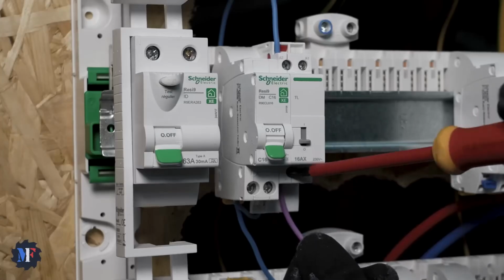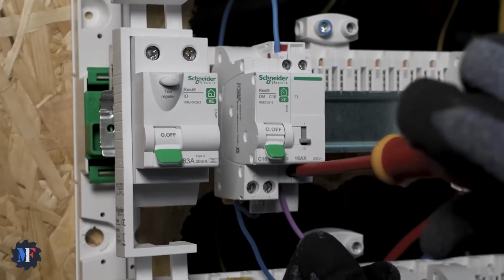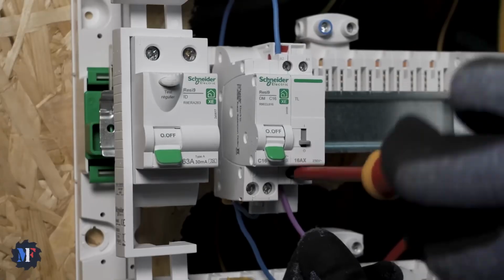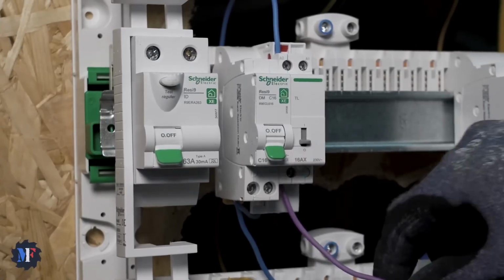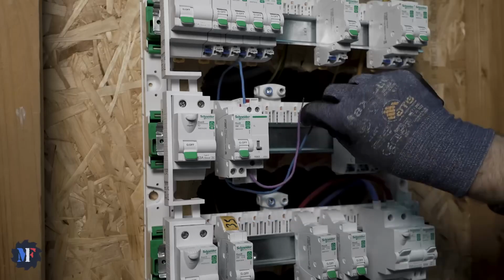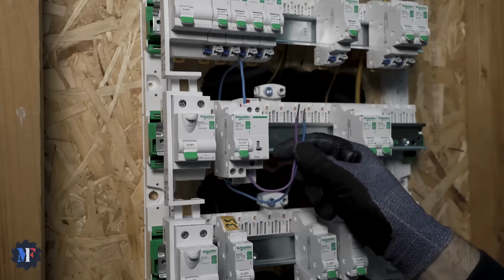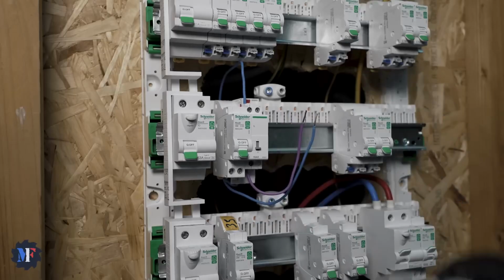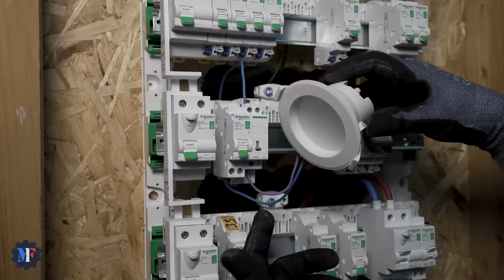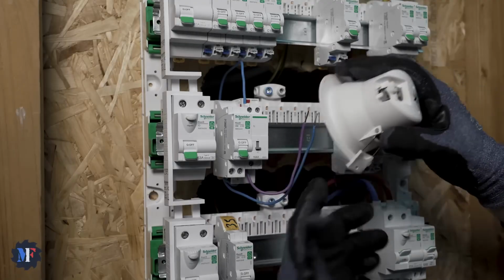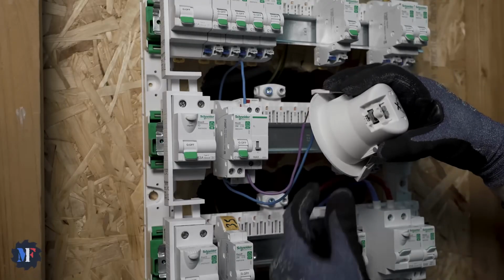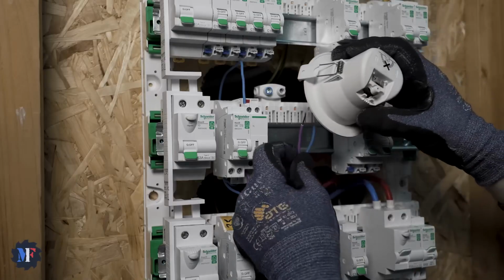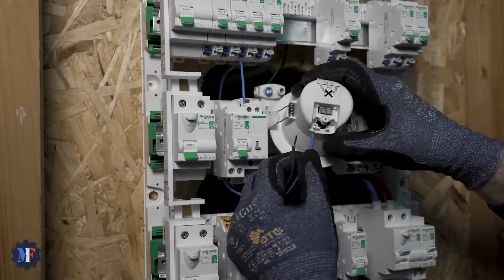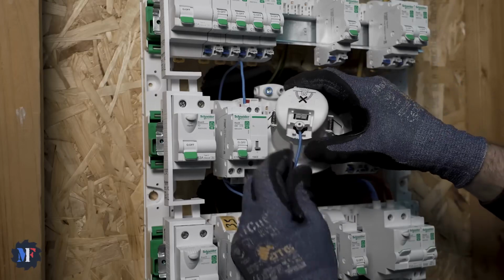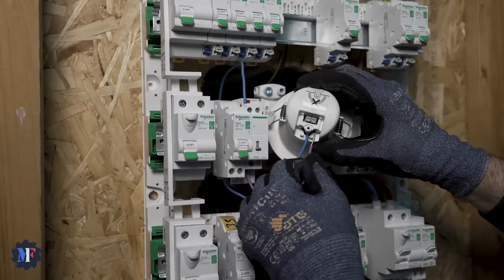As I mentioned, I'm keeping the colors like with the step relay. The big one here is purple, but you can use whatever color you want. So I end up with the blue and the purple wire for my light point. My spotlight is plastic, so I don't need the ground wire. If your light point needs a ground wire, connect it directly to the ground terminal block, but that's not the case with my light point. The neutral goes on the neutral and the purple wire goes on the live.